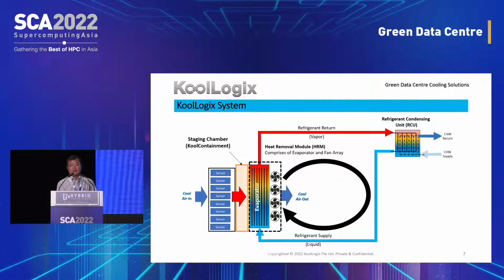So the vapor refrigerant goes up, just like steam goes up in nature, and then goes to the RCU, the refrigerant condensing unit, away from the white space. Okay? Then it gets condensed by losing the heat into the chilled water supply, and the liquid refrigerant falls down by gravity and goes back down to the evaporator, and this cycle goes around. We do have an array of fans attached behind the heat exchanger to assist the airflow through the racks, so we can actually control the performance of this heat removal capability.